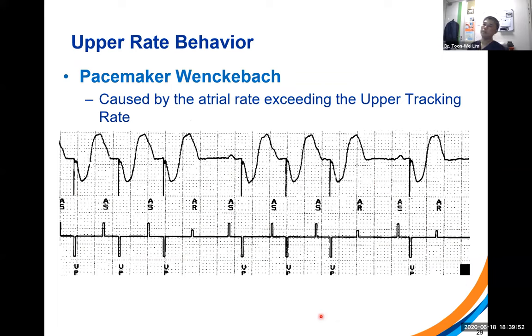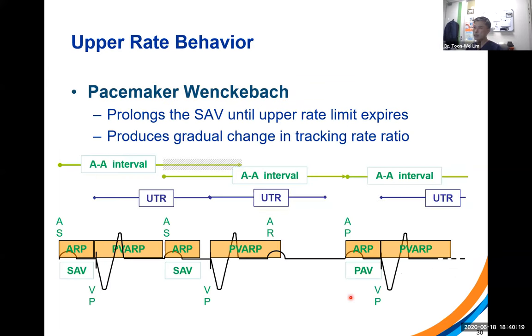But basically what happens is that the A-sense V-pace interval gradually prolongs until, because the V-pace comes in so late, the next atrial activity or sinus beat falls into the PVARP and is then considered refractory, and no pacing follows on from that. And as such, you have this pattern that looks exactly like a Wenckebach pattern. And the reason for that is this.